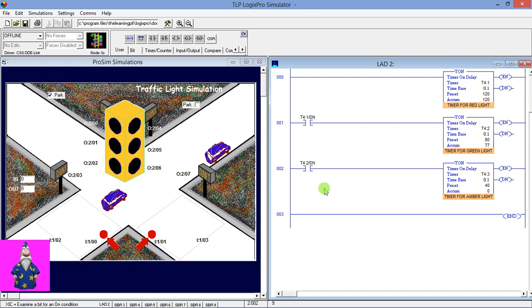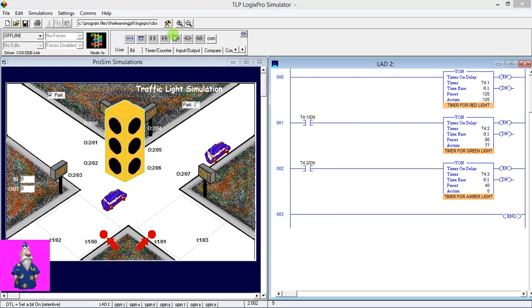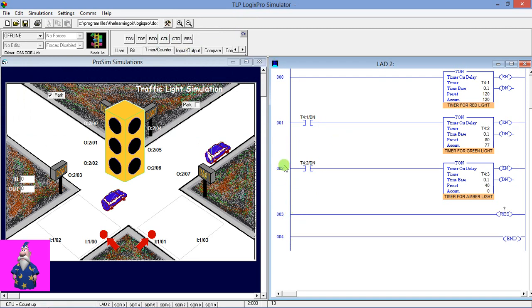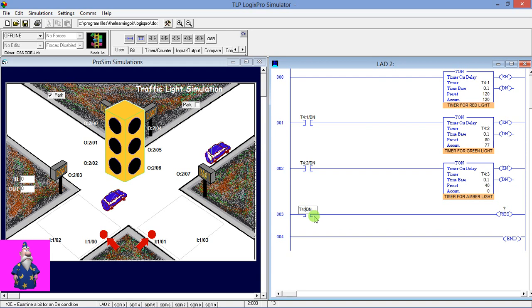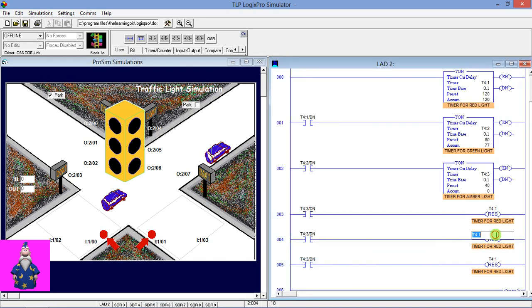We have to do this function in a loop or in a circle, so we have to reset all these timers using the done bit of timer number three. We're going to use the Reset instruction here, driven by the done bit of timer three. Change the address to timer three and give the addresses of all timers — starting with the red light timer — then copy and paste three times, changing to timer one, timer two, and timer three.